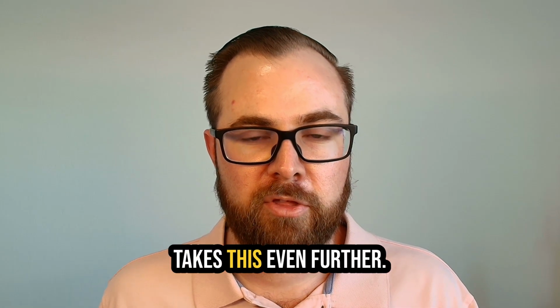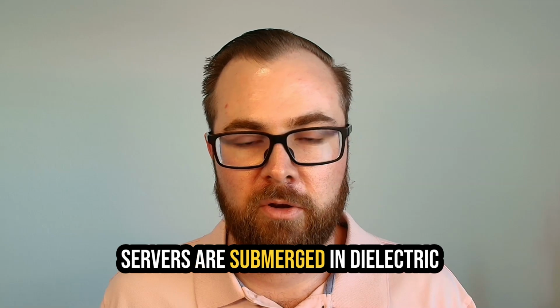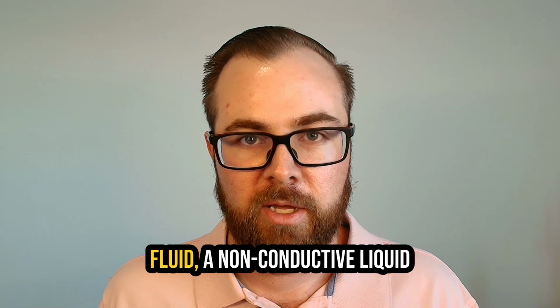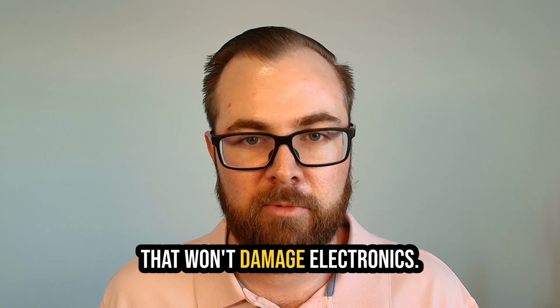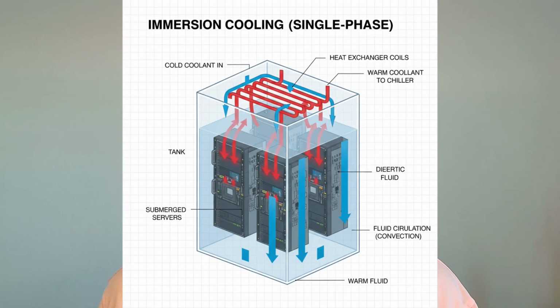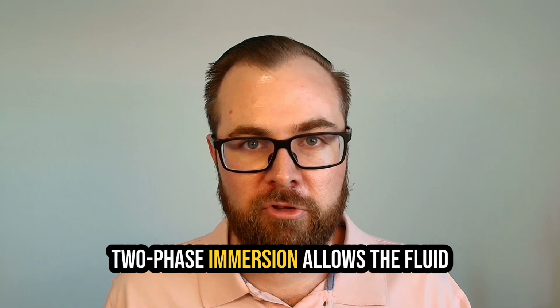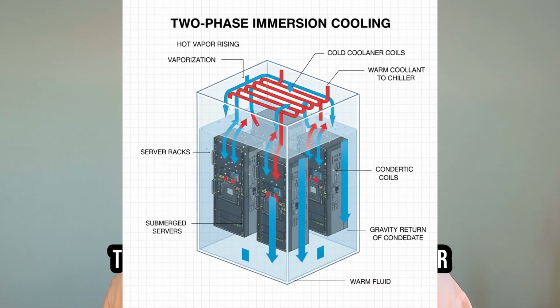Immersion cooling takes this even further. Servers are submerged in dielectric fluid, a non-conductive liquid that won't damage electronics. The fluid absorbs heat directly from all components, eliminating the need for fans and dramatically reducing energy consumption. Single-phase immersion keeps the fluid liquid. Two-phase immersion allows the fluid to boil, which provides an even better heat transfer through phase change.